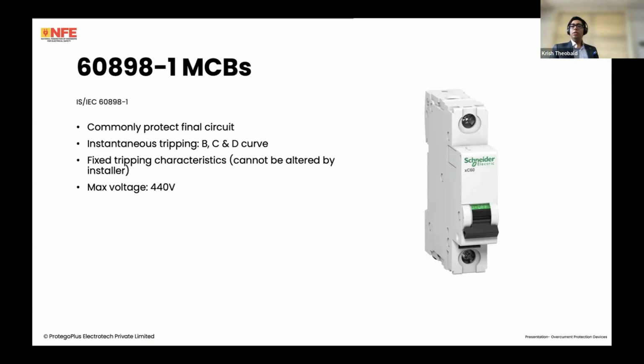It's fixed. The maximum voltage is 440 volts. That's line to line or phase to phase. That's what the 60898 Part 1 MCB is certified for.